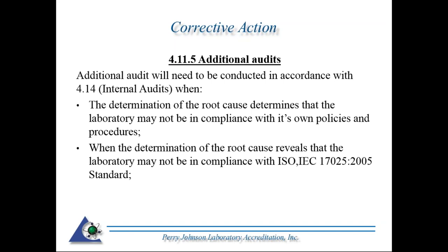17025, which leads to the second reason in which corrective action may incorporate an additional audit: when the determination of the root cause reveals that a laboratory may not be compliant with the ISO/IEC 17025:2005 standard.